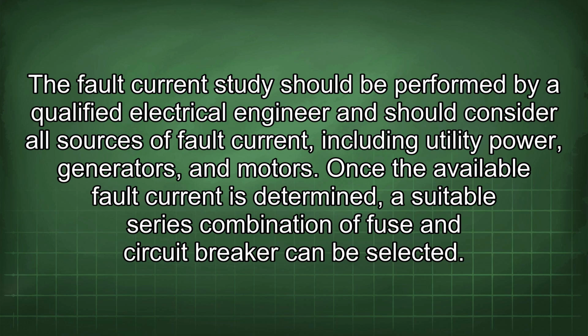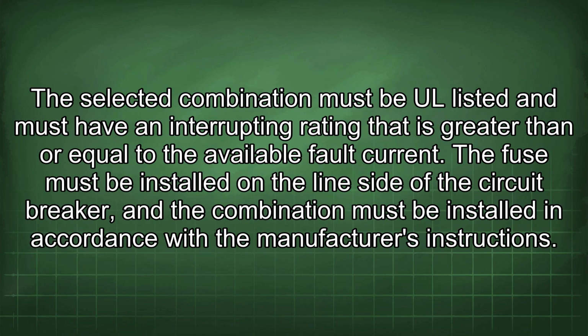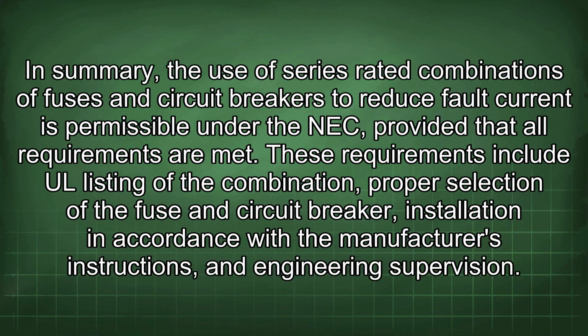Once the available fault current is determined, a suitable series combination of fuse and circuit breaker can be selected. The selected combination must be UL listed and must have an interrupting rating that is greater than or equal to the available fault current. The fuse must be installed on the line side of the circuit breaker, and the combination must be installed in accordance with the manufacturer's instructions. In summary, the use of series-rated combinations of fuses and circuit breakers to reduce fault current is permissible under the NEC, provided that all requirements are met.